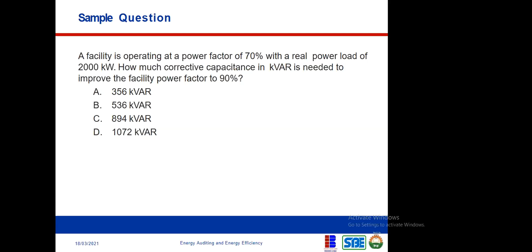So this is a sample question. A facility is operating at a power factor of 70% or 0.7, with a real power load of 2000 kilowatts. So you know the true load, 2000 kilowatts, and you know the power factor, 70% or 0.7. How much corrective capacitance in kVAR is needed to improve the facility power factor to 90% or 0.9? So there are options here. Let's go down to the next slide.